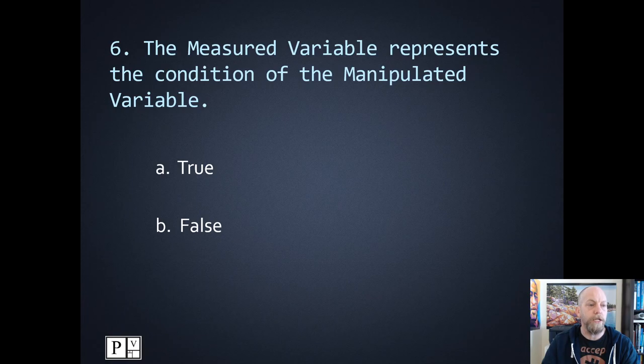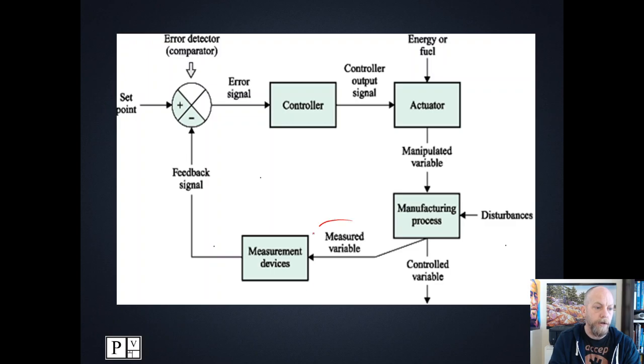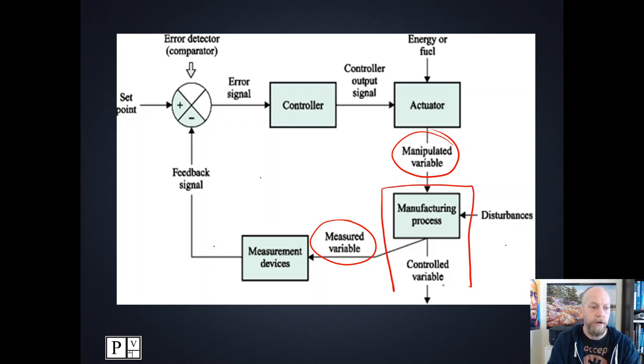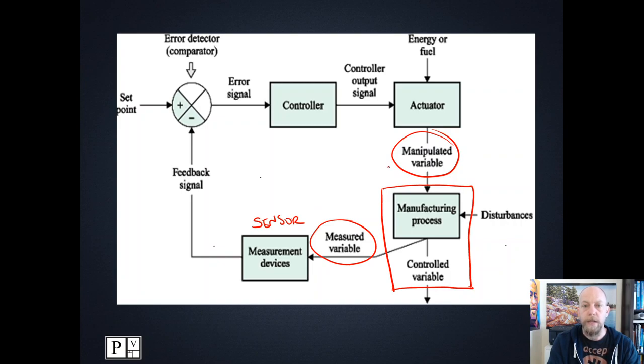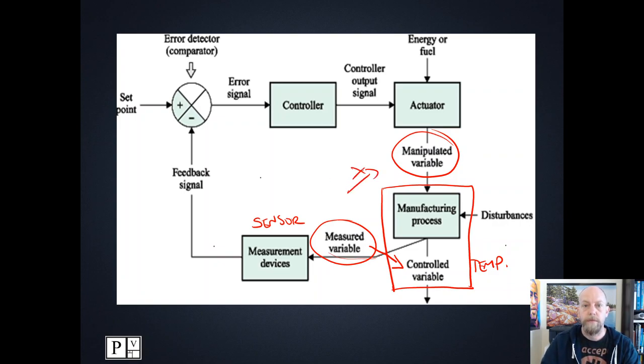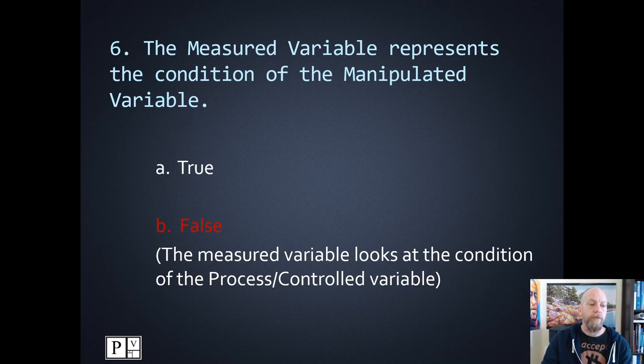Number six: the measured variable represents the condition of the manipulated variable. The measured variable is right here and we're saying it looks at the manipulated variable — but there's something in between. The manipulated variable is like steam flow; you're manipulating steam flow to ultimately control temperature. The measured variable is what your sensor is looking at. Your sensor is measuring the temperature — the controlled variable — not the steam flow. So the measurement device is looking at our control variable, not the manipulated variable. This one is false.